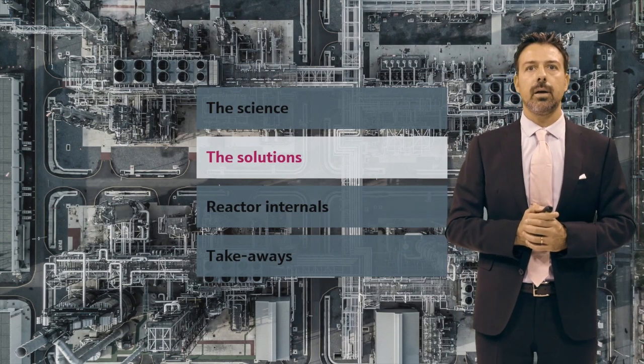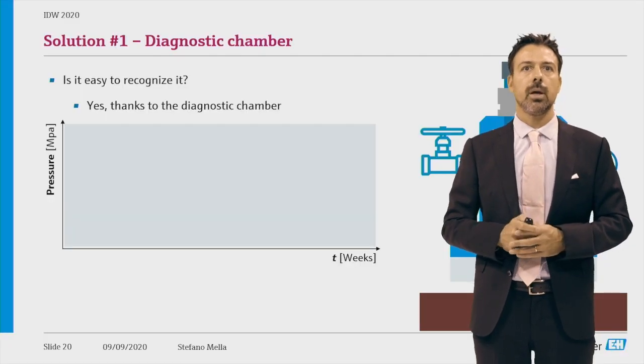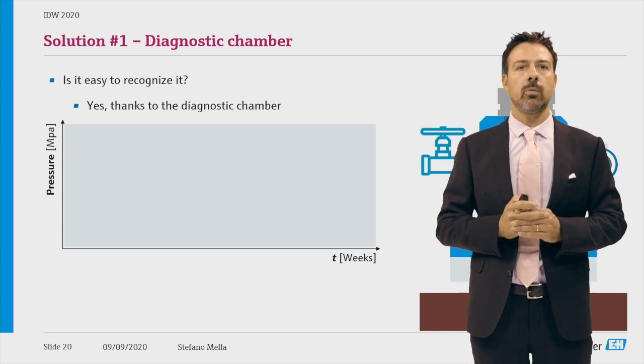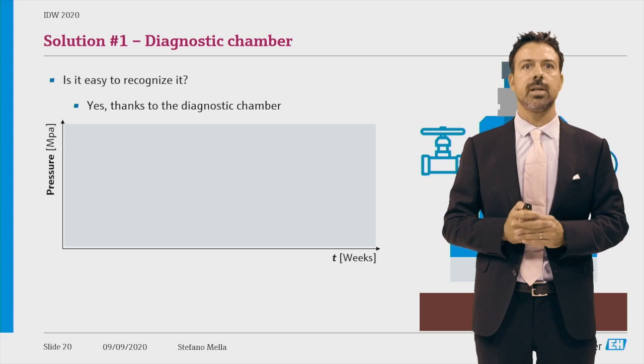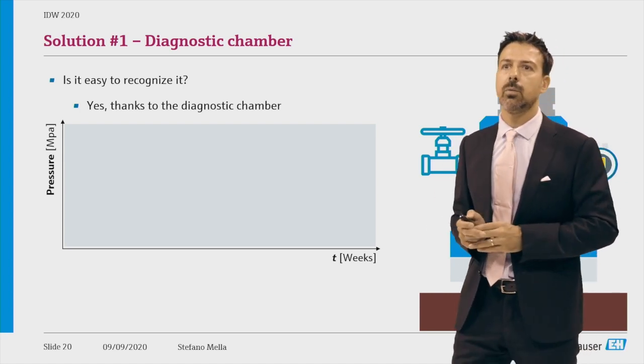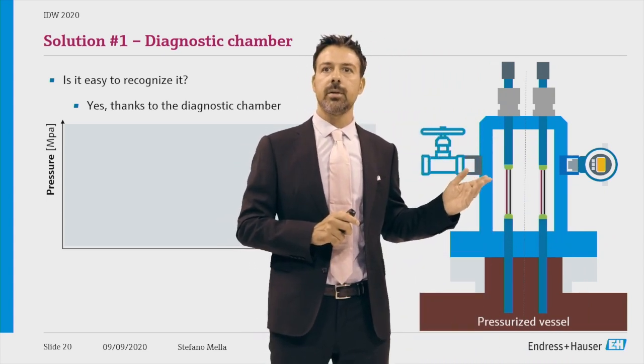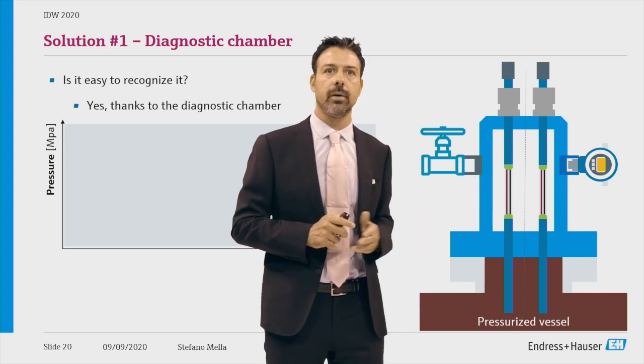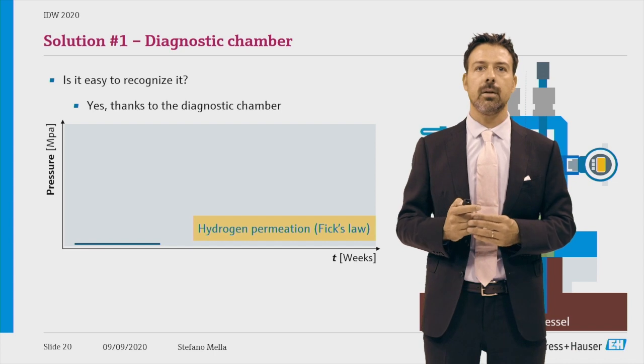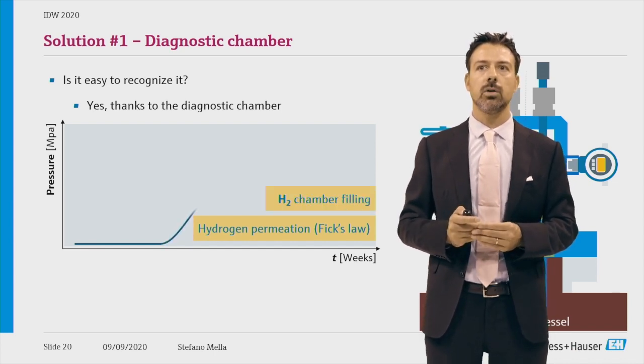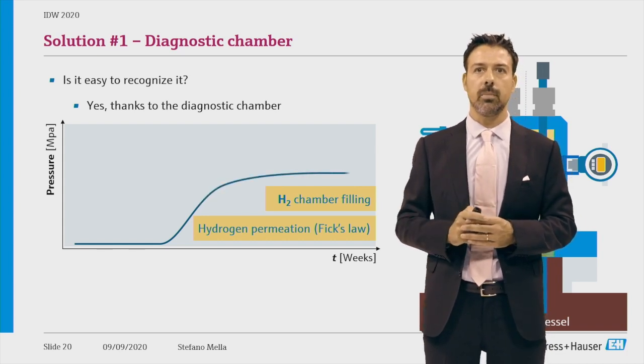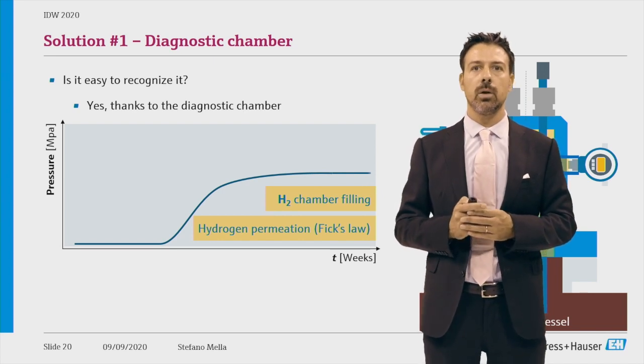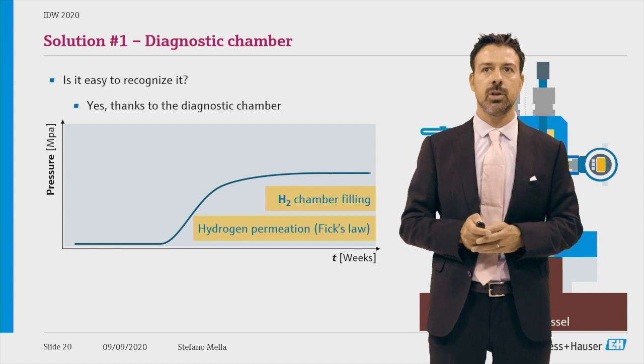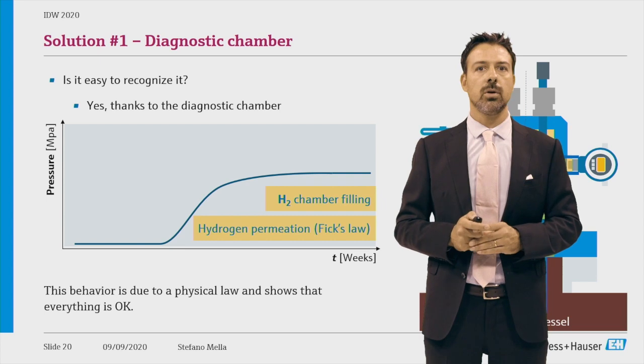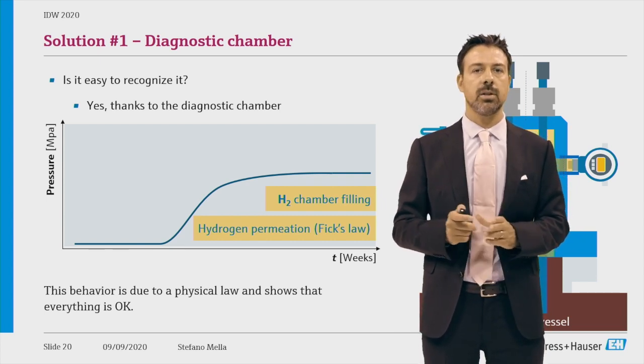As I said, we don't want just to explain the science behind the problem, but also the solution. The first question you might have is, how can I recognize that something like what you have described is happening in the plant? Our suggestion is to use our diagnostic features. Here you see a thermometer with a diagnostic chamber, the blue volume here. And you have to look at the pressure trend over time. We will have hydrogen permeating through the metal flange, and it's a matter of time before the hydrogen also occupies the volume inside the diagnostic chamber. When the diagnostic chamber is full of hydrogen, it will reach its equilibrium, which is called the hydrogen partial pressure. Something important: this behavior is due to a physical law and shows that everything is okay. In other words, there's nothing to worry about.